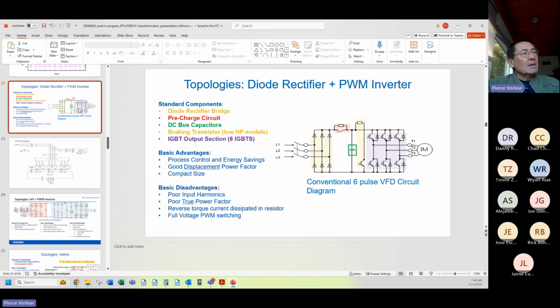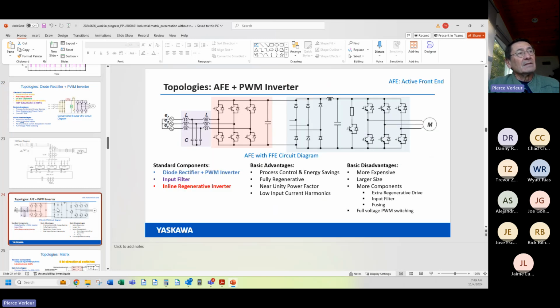Going back to this, anything happening here on the line in terms of power factor and distortion is not seen by the motor. Why? Because you have a DC bus heavily filtered with big capacitors that basically puts an electric barrier right here between the input and the output. The motor doesn't see what's going on the line. Period. That's the fact.